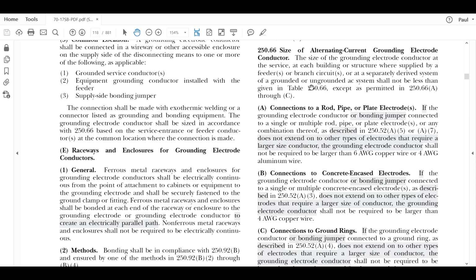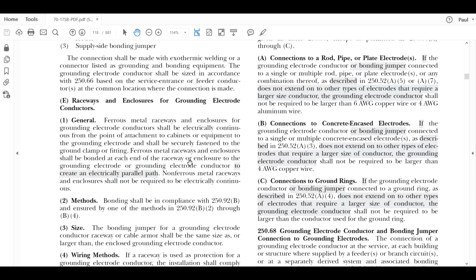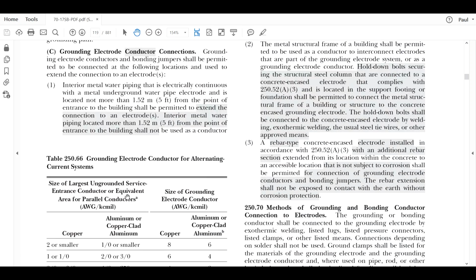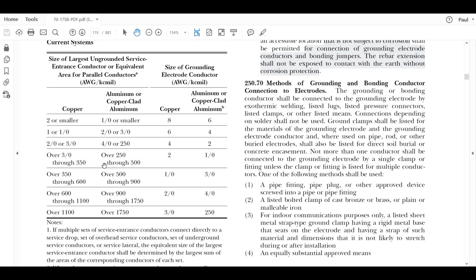But let's say it was a water pipe ground or in-ground steel. Then you would use the table. And you go down here to the table. Now, this is, again, going to be based on those derived conductors. Okay. And in our case here, it was 3/0 through 350, so it would be a 2. And that's what you would run to that electrode if it wasn't one of the ones that allow for smaller ones. Okay? Notice this table looks very similar to 250.102(C) because 250.102(C) was derived from this table.